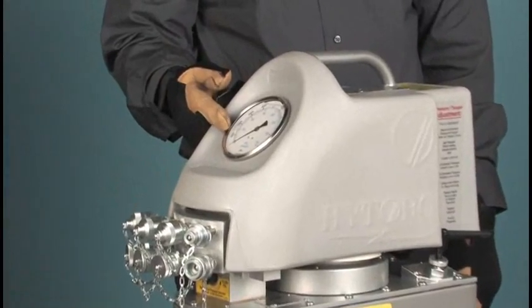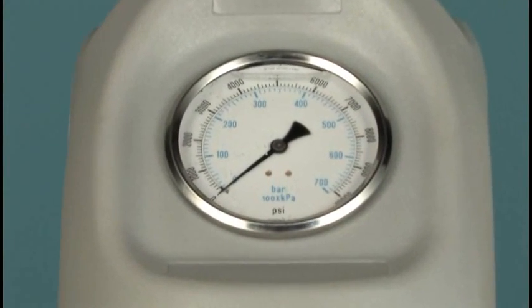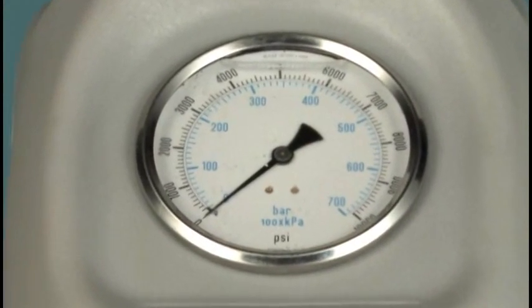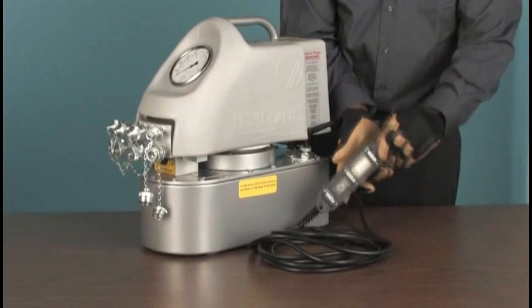Output pressure is measured on a gauge which is calibrated to plus or minus three percent accuracy when new. Most gauges can and should be recalibrated usually at least once per year if they are to be used on critical work where accuracy is essential.